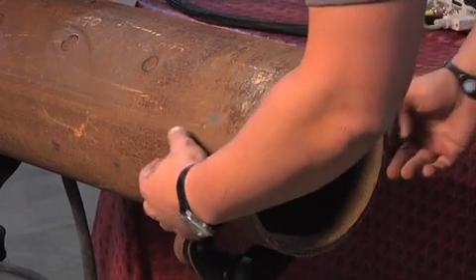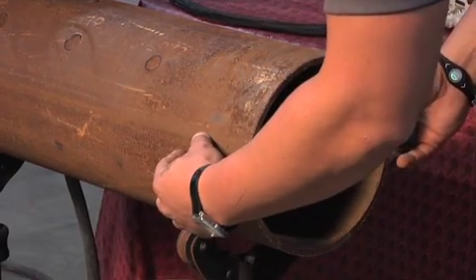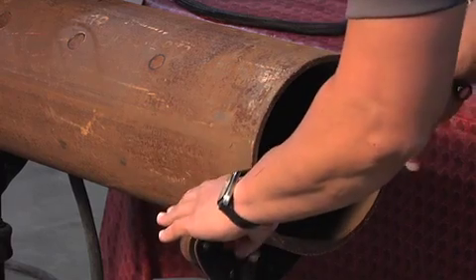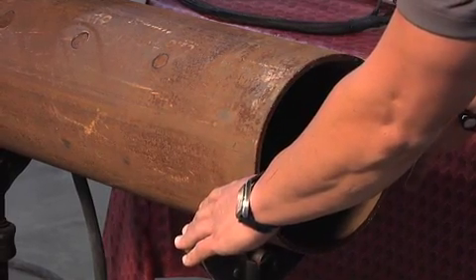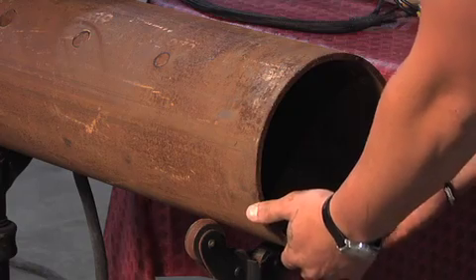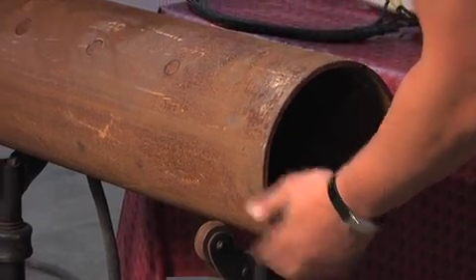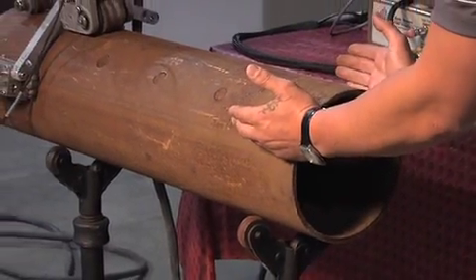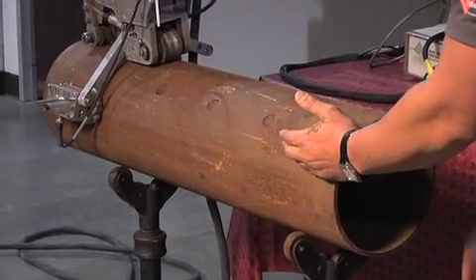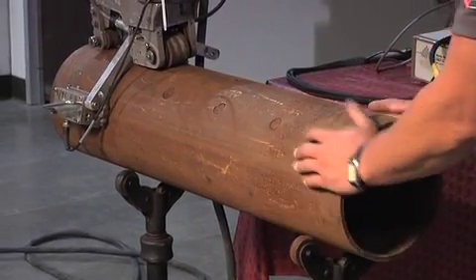And at the soil and at the earth bank, you can see scale, exfoliation, corrosion from the atmosphere, from rainwater. And instead of the client or customer having to dig out the pipe, we could access the top section. Just 1/3 of the pipe is required, and we do a full volumetric inspection of the pipe without disturbing the soil.